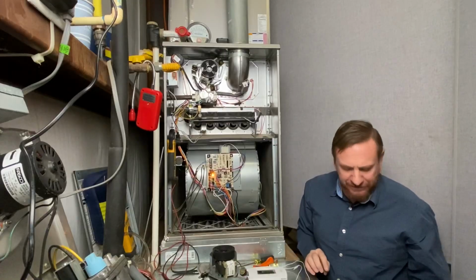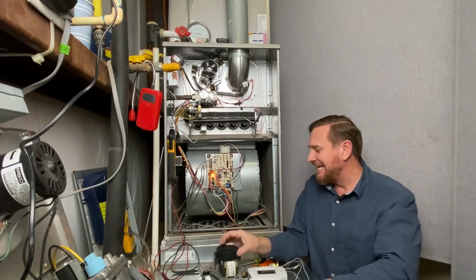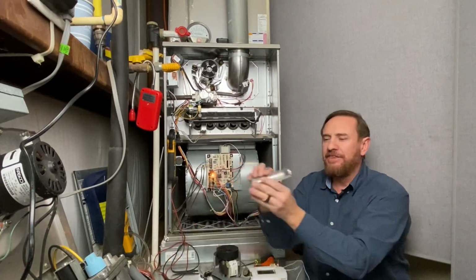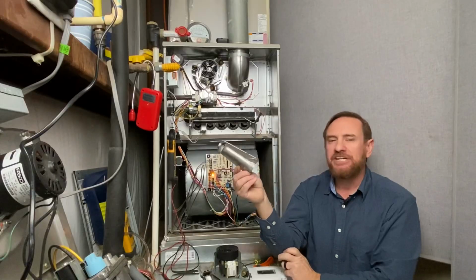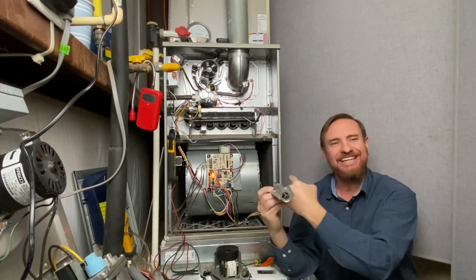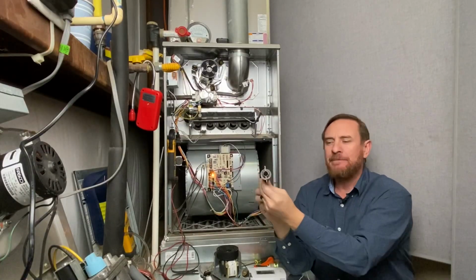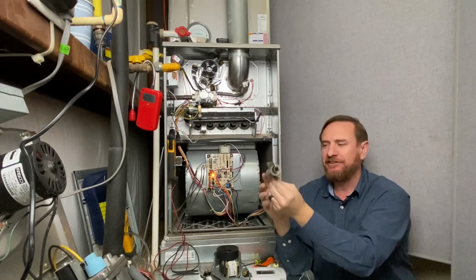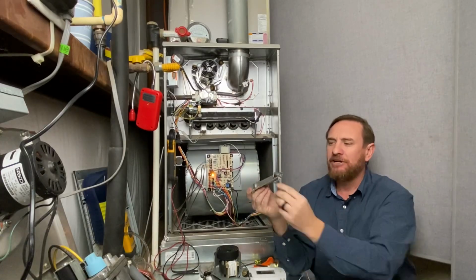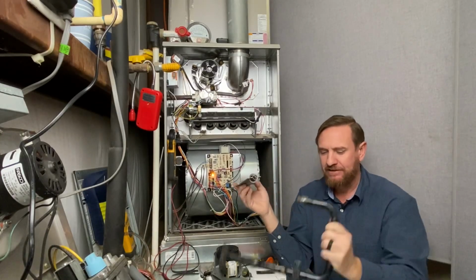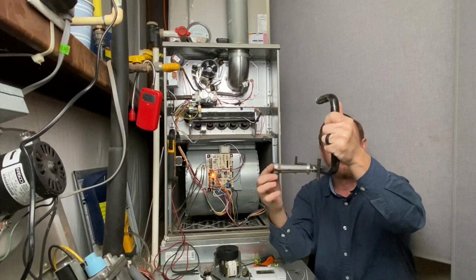Now the type of burners that we're going to be using is called an in-shot burner. So this is a burner. It's called an in-shot burner. It's shooting the gas into our heat exchanger. A lot of people call these jets. That's perfectly fine. It is an in-shot burner. So the spud and the burner hook together.